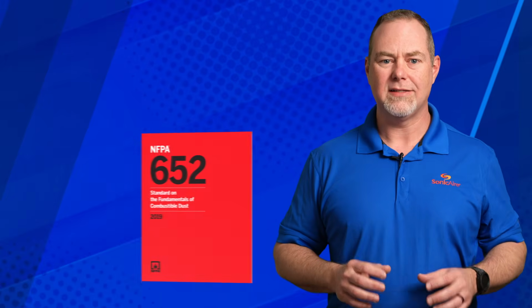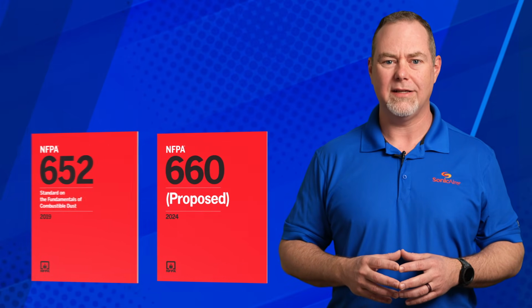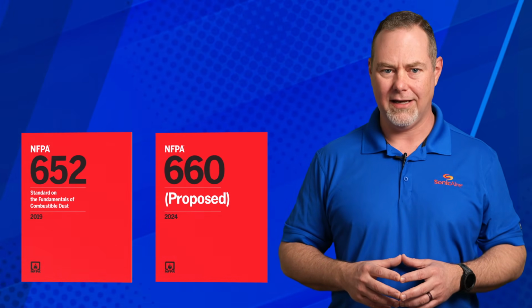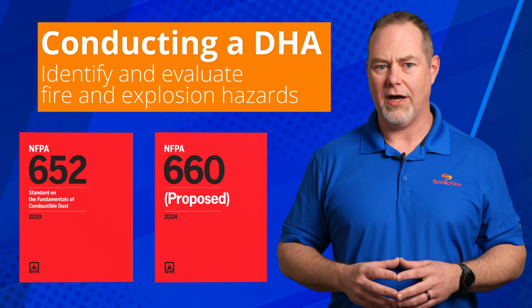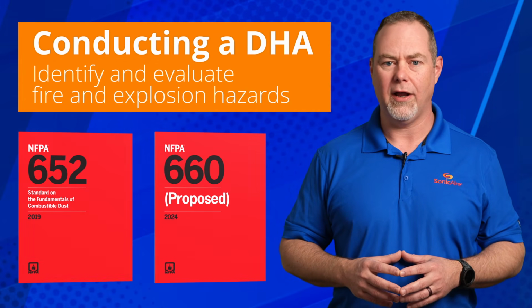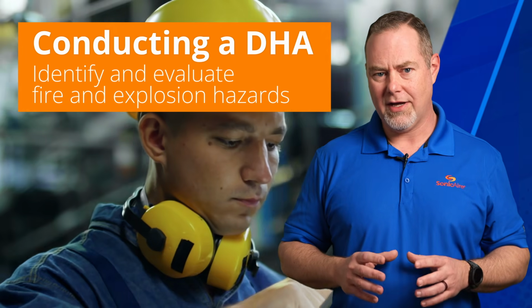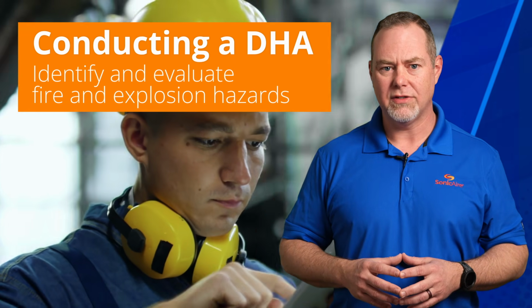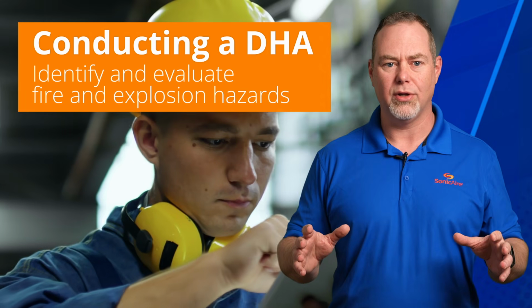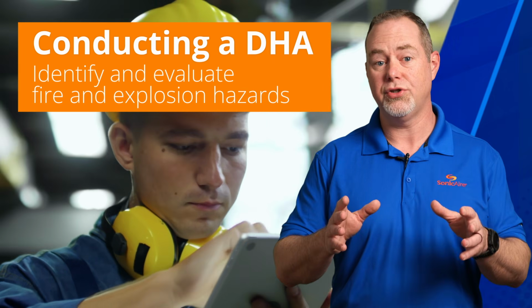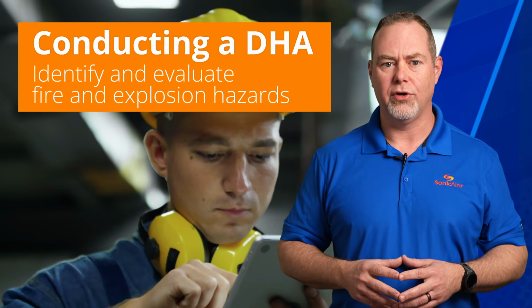Using NFPA 652 or NFPA 660 as a guide, you'll need to identify and evaluate any process or area where a fire or explosion hazard exists. Identify and document the safe operating ranges, any safeguards currently in place, as well as any safeguards that should be implemented, and a plan for doing so.